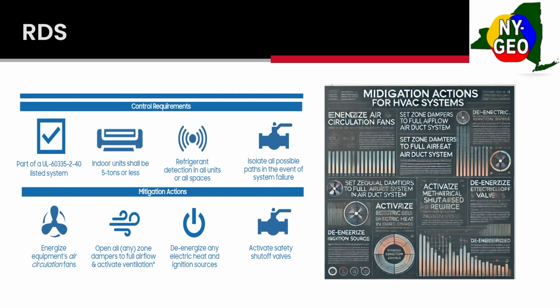So what are the mitigation actions when the RDS goes off? The first thing it does is shut off the compressor and turn on the fan to circulate the air. If you have a mitigation system, it's going to initiate that exhaust system. It's going to open all zone dampers. So if you have a VAV system, anything like that, it's going to open all the zone dampers. Any electric heat, any electric source in the ductwork, it's going to de-energize, and obviously close off your safety valves. It's going to do this for 5 minutes. Test again, reset, and the alarm will go off again. And most likely, if it goes off a second or third time, the unit's probably out of refrigerant and tripping on low pressure.